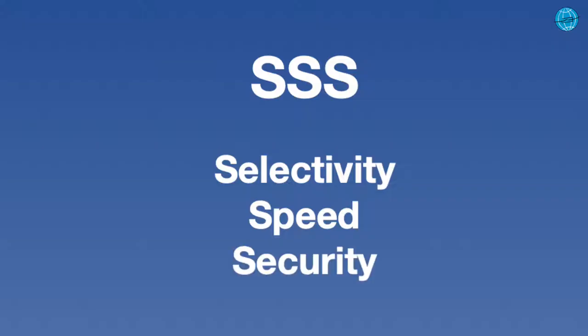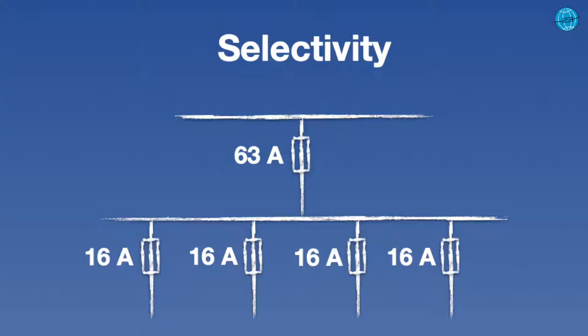The 3S of electrical protection engineering are selectivity, speed and security. Selectivity ensures that only faulty or endangered equipment is switched off and the remaining system parts can continue to be operated. In order to be selective, it makes sense to detect fault location and type of fault using the protection system.